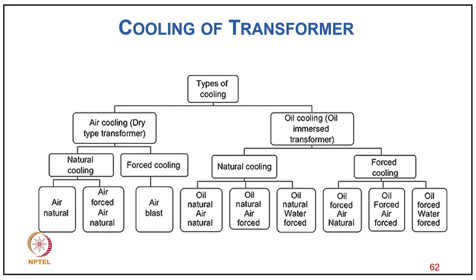Types of cooling for transformers: for dry-type transformers, natural air cooling (AN) or forced air cooling (AF/air blast). For oil-immersed transformers: natural oil cooling (ONAN), oil natural air forced (ONAF), oil natural water forced (ONWF), oil forced air natural (OFAN), oil forced air forced (OFAF), and oil forced water forced (OFWF). As the rating increases, more sophisticated cooling is required.